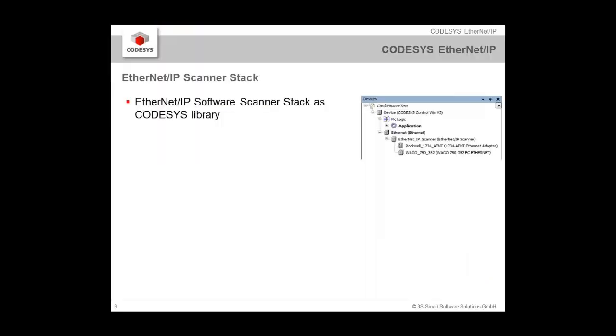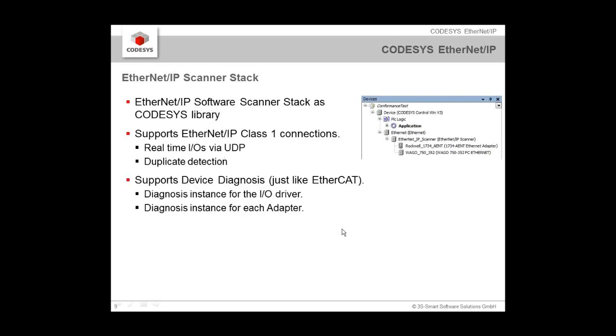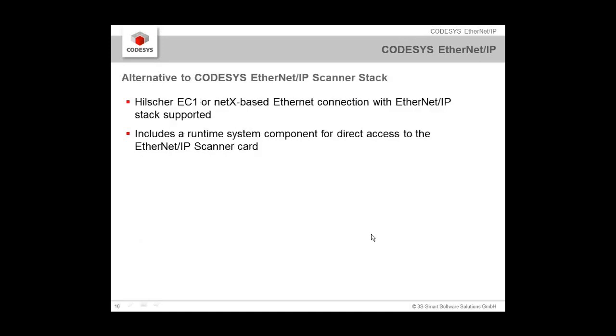Let's come back to the presentation. We see that the EtherNet/IP software scanner stack really realizes the whole protocol just by the means of a CODESYS library. It supports class 1 connection, so we have real-time inputs and outputs via UDP. We have a duplicate detection and we have as well support device diagnosis. We have seen that with its symbols. We see diagnostic instances for the IO driver and for each adapter. One component in the runtime system of the PLC is necessary. It's the syssocket component which needs to be implemented. But usually this is realized as soon as you have an Ethernet port on your device.